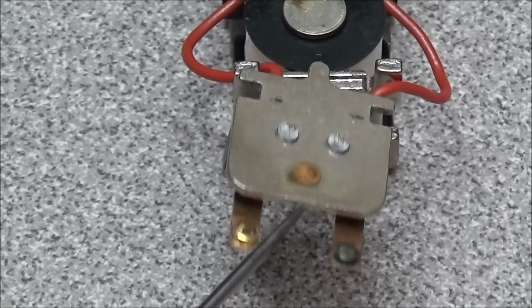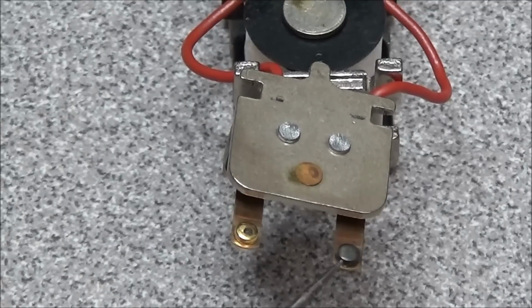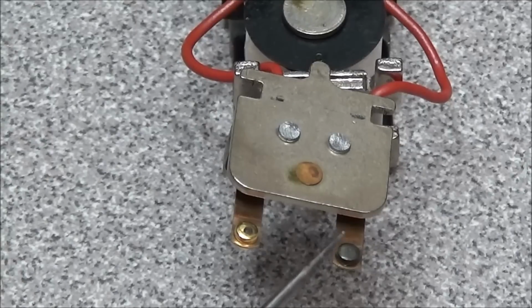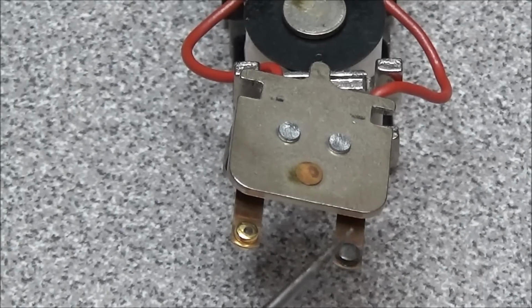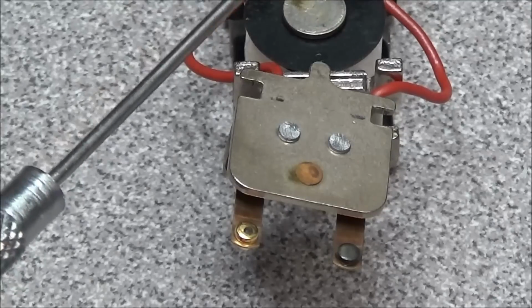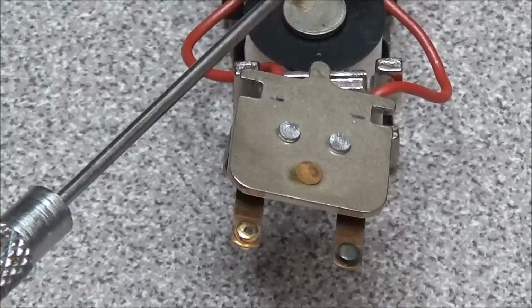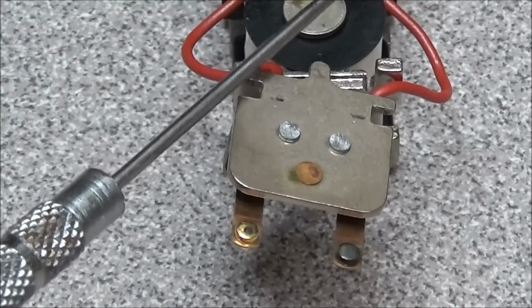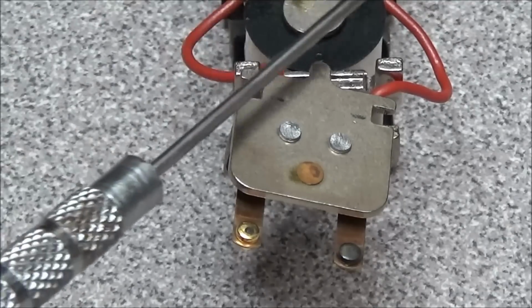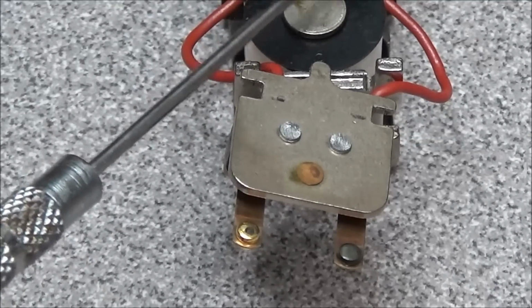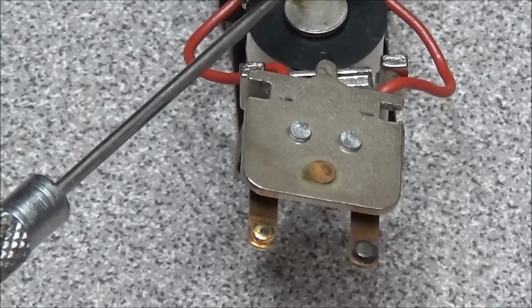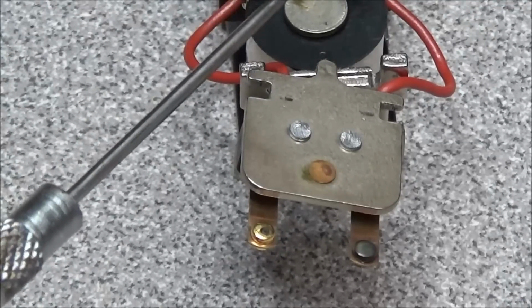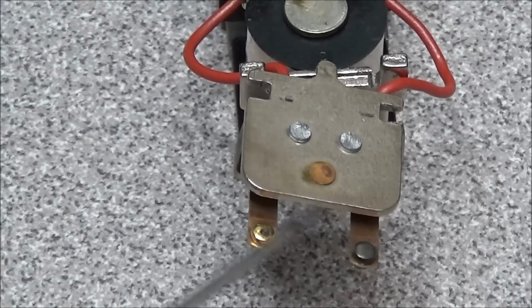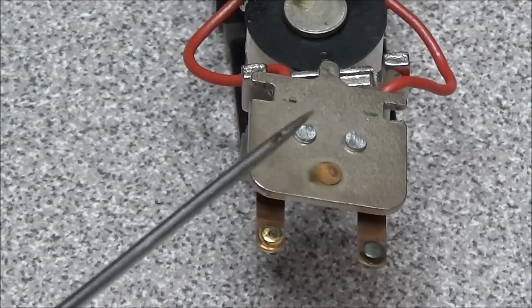When you're cleaning relays, do not use sandpaper or a file. The best thing I like to use is a pencil eraser, because that will take all this tarnish off. You can also put the relay back together, take a piece of paper, coat it in deoxit or contact cleaner, and push the relay in and run it through back and forth, and that will clean it off. Then switch to the other side and engage the relay with your hand and run that paper back and forth. This way you're not damaging the contact. The contact has a coating on them, and if you ever wear that coating out, the relay will go bad.